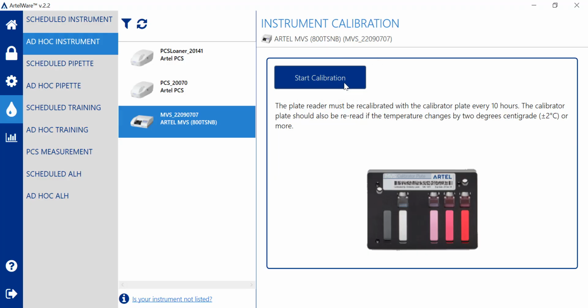You'll see a note here that the calibrator plate has to be run every 10 hours. That's the same amount of time for the baseline plate as well. So if those items haven't been run in the last 10 hours, the system will require you to do that. Let's go ahead and click Start Calibration.